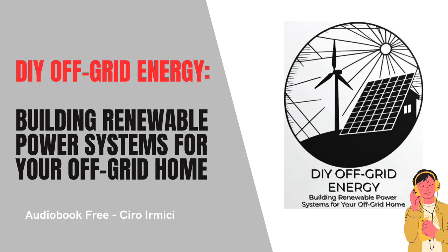Integrating inverters with batteries and renewable sources. Integration is a vital aspect of setting up your off-grid inverter system, as it involves connecting the inverter to your batteries, renewable sources, and the household electrical panel. Proper integration ensures that power flows efficiently between generation, storage, and consumption, maintaining a stable and reliable supply of electricity. The connection between the inverter and your battery bank is particularly important. The inverter must be compatible with the battery's voltage and capacity, as mismatches can lead to poor performance or even system failure.